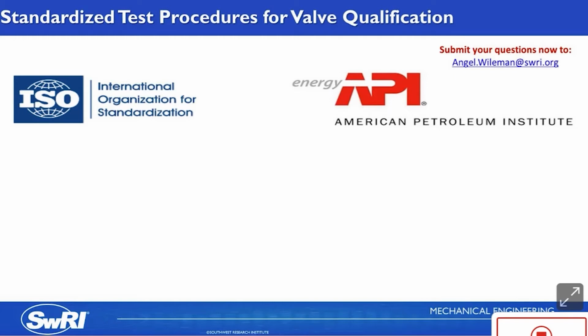But there has to be some type of industry recognized standard to follow when qualifying the valves, or else any valve manufacturer could come up with a procedure, stamp their valve good to go, and there would be no consistency between test methods or passing criteria. So end users specify standardized fugitive emission procedures that they must qualify their valves to in order to install them.